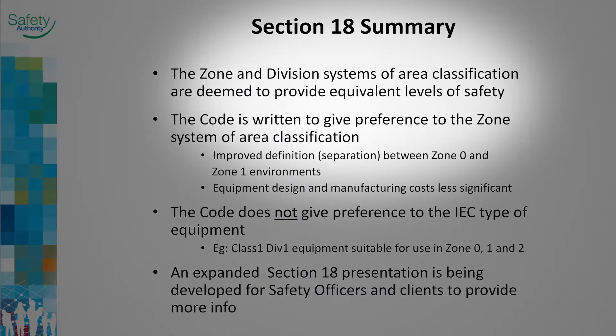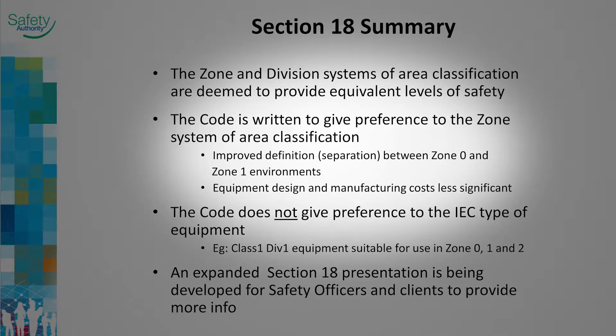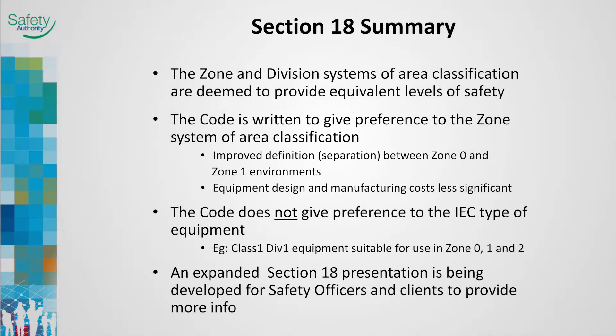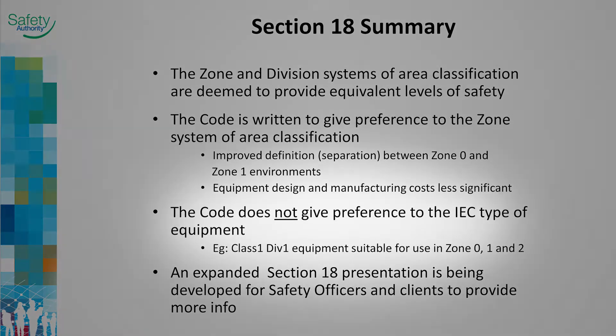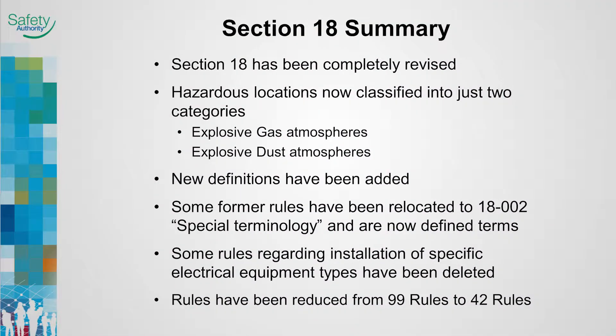It has been determined that the Zone and Division Systems of Area Classification in Section 18 provide equivalent levels of safety. Preference is given to the Zone System of Area Classification. The Code does not give preference to the IEC type of equipment. Section 18 has been completely revised.